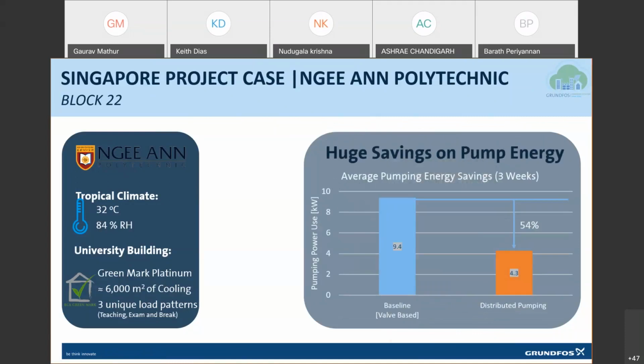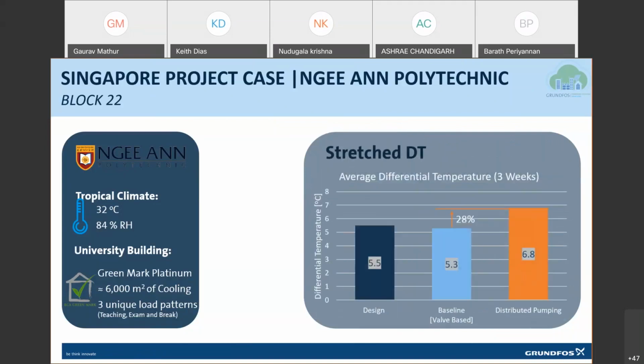This is the amount of savings we achieved from the baseline. And we have been able to achieve more than 50% saving on the pumping cost. We also saw an improvement in the delta T of the overall system because it's a temperature-based control. But this is something which can vary from site to site. So we do not really say that these are the kind of savings we can attribute to any site. But this is a very important point for us to mention, that when you have a temperature-based control in the system, it does improve the efficiency of the chiller. And that is where you can see how the connect is happening when you have an approach which is only equipment based compared to an approach which is system based.